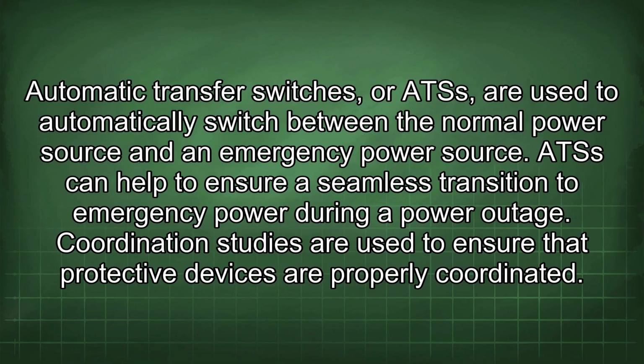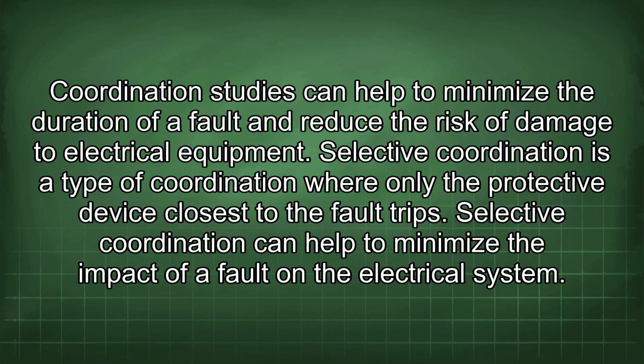Automatic transfer switches, or ATSs, are used to automatically switch between the normal power source and an emergency power source. ATS can help to ensure a seamless transition to emergency power during a power outage. Coordination studies are used to ensure that protective devices are properly coordinated. Coordination studies can help to minimize the duration of a fault and reduce the risk of damage to electrical equipment.